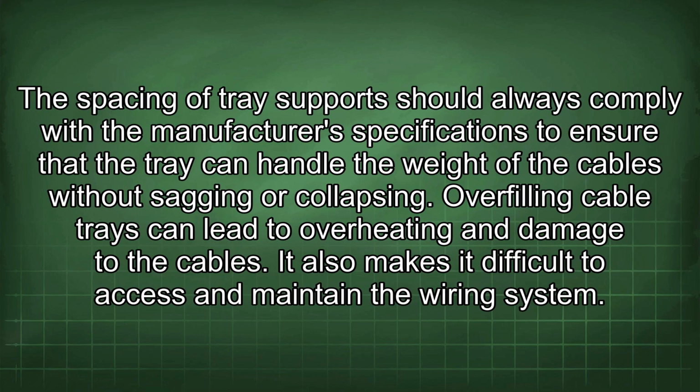The spacing of tray support should always comply with the manufacturer's specifications to ensure that the tray can handle the weight of the cables without sagging or collapsing. Overfilling cable trays can lead to overheating and damage to the cables. It also makes it difficult to access and maintain the wiring system.